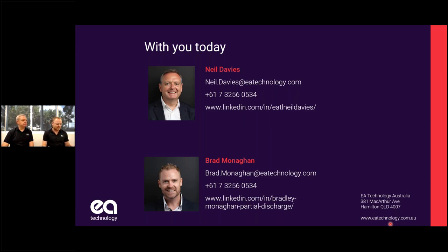And one last question, because we've just gone 6 minutes over time. What would cause high ultrasonic and TEV to be there one day and then completely disappear the next day? Usually humidity and movement, usually. Yeah, there you go. Brad's answered that. Humidity and movement. Do you want to answer it more, Brad?